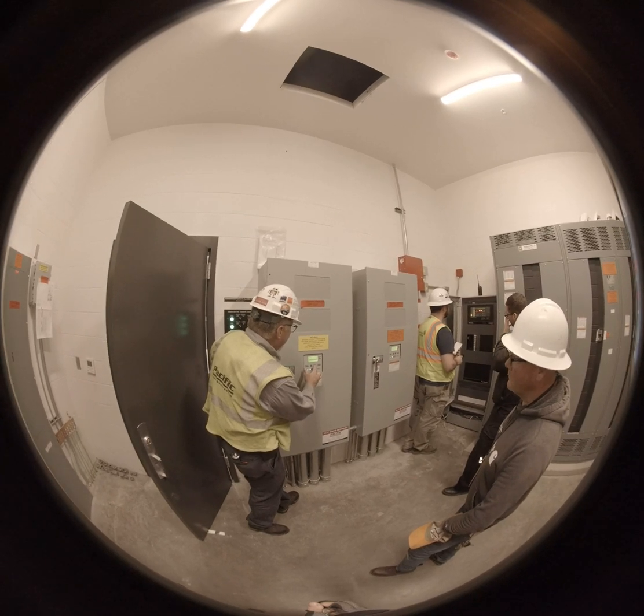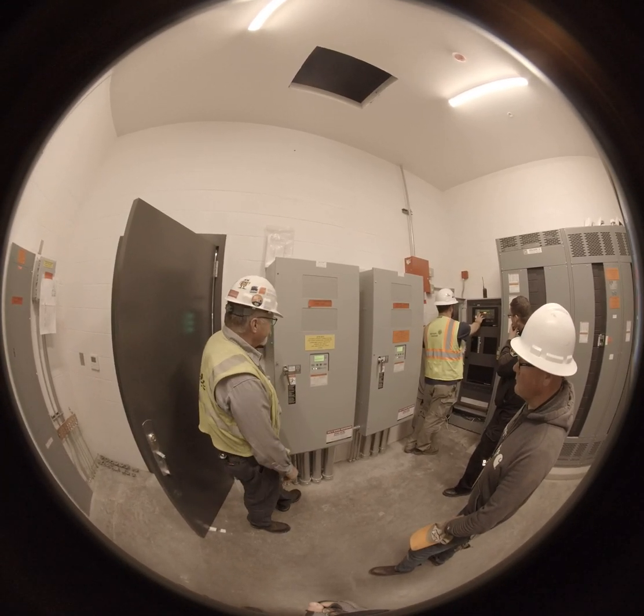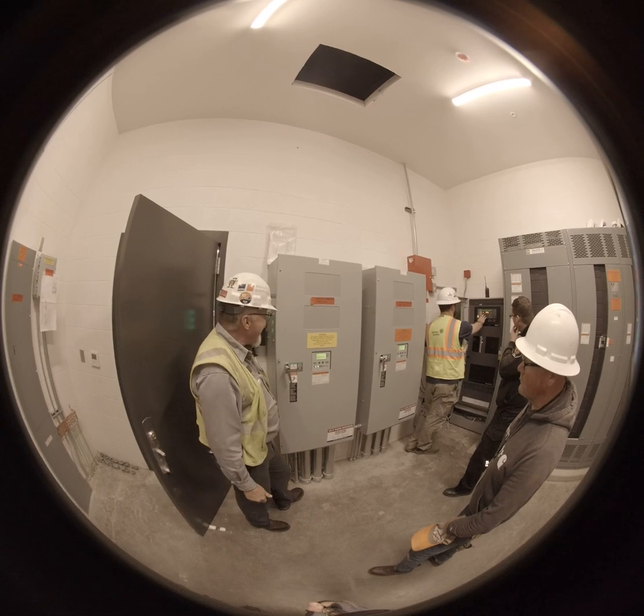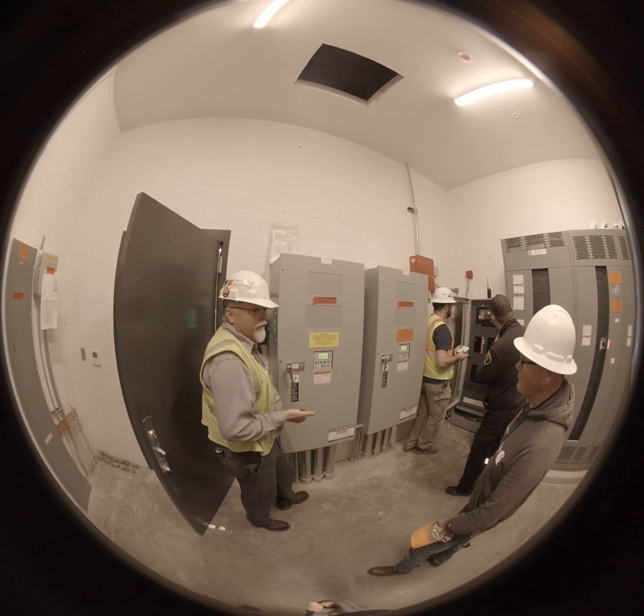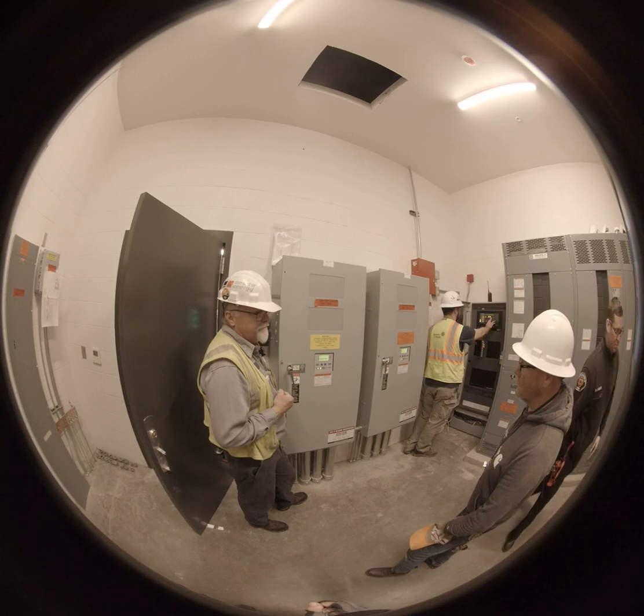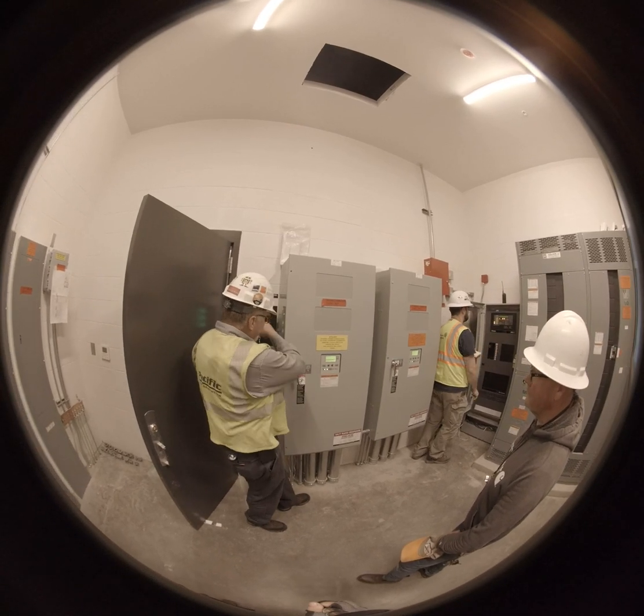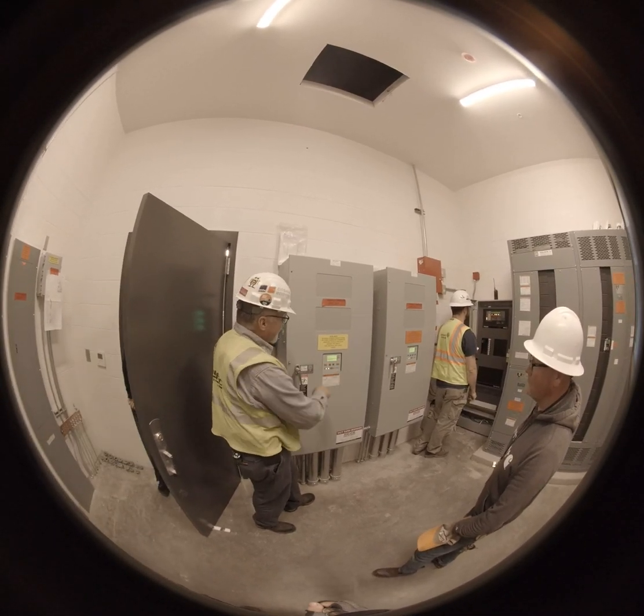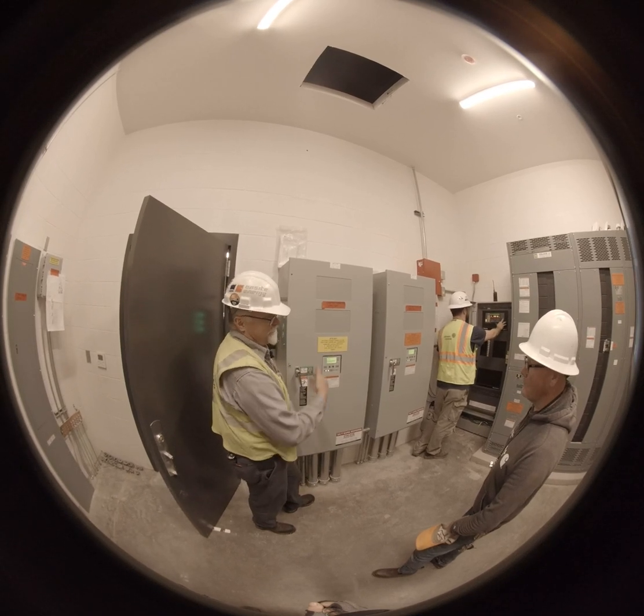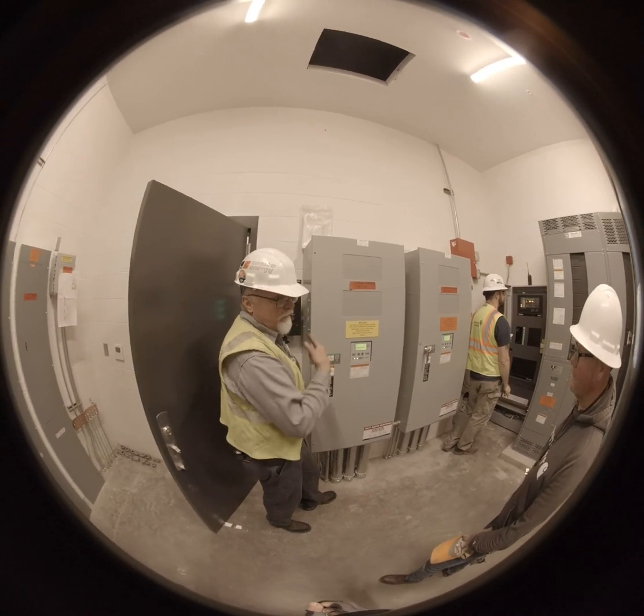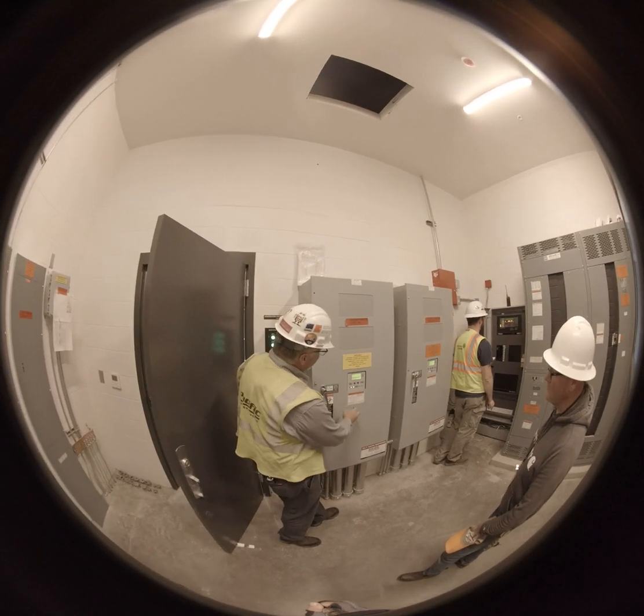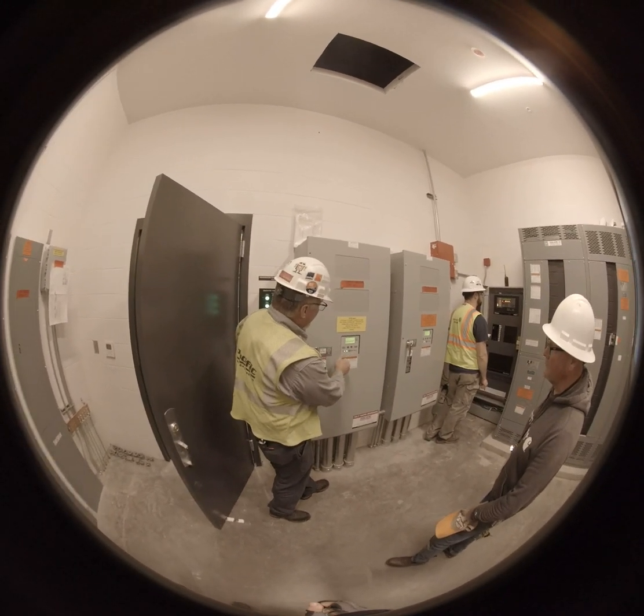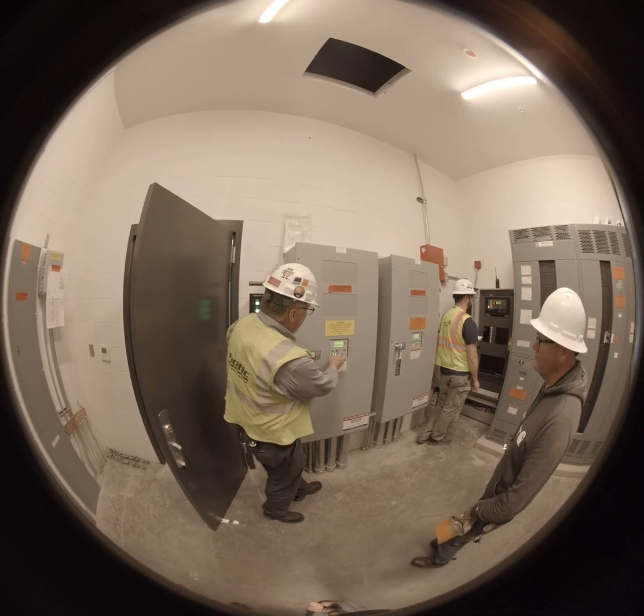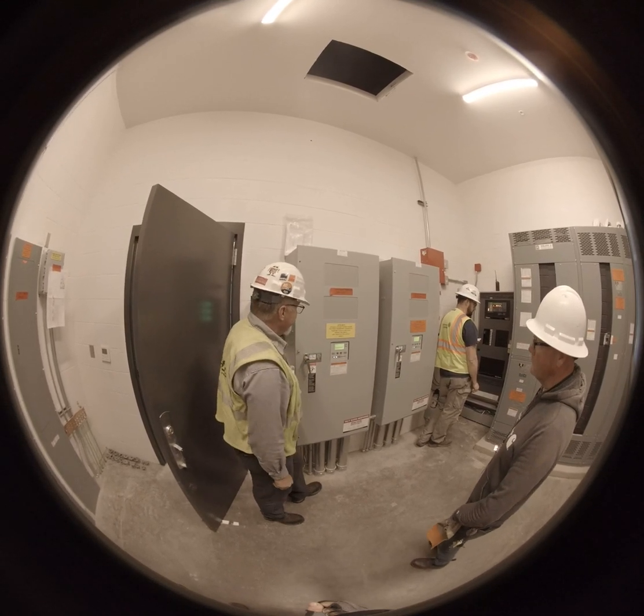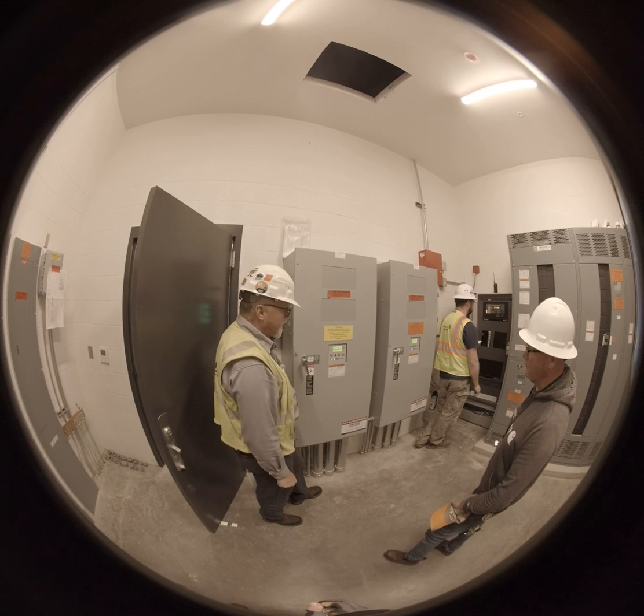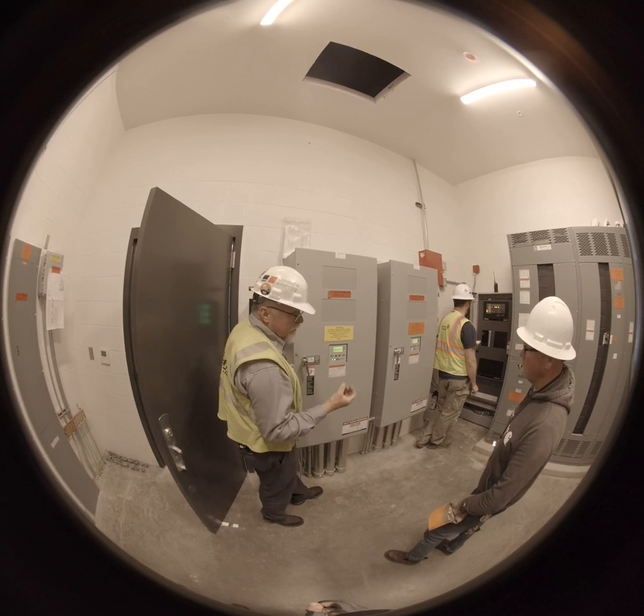The trick to that one is on the other direction. So emergency back to normal in an actual outage, it's going to run for 5 minutes to proof utility. Whereas if you use the test switch here, it's going to run for 30 seconds, because you know utility is good. You just told it you wanted to transfer. And that's that one right there. Then generator cooldown is at 5 minutes.